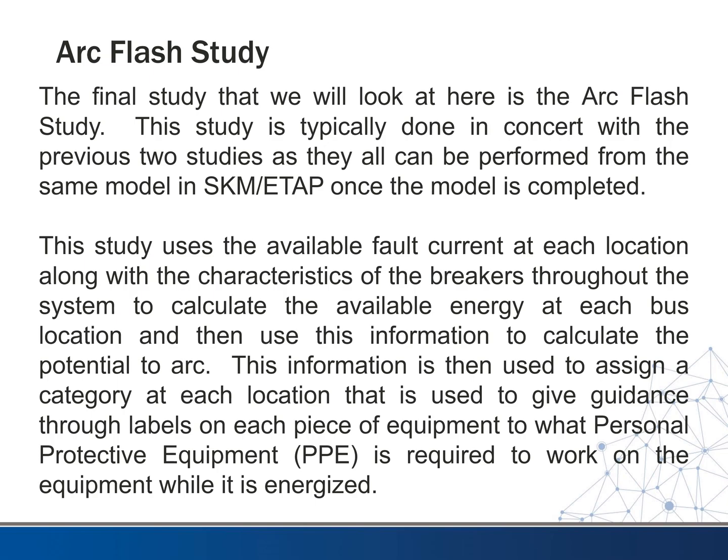This category gives guidance through labels placed on each piece of equipment as to what type of PPE — personal protective equipment — is required for an electrician to work on that equipment while it's energized and stay safe. It's a pretty important study. It is required by OSHA. If you have a facility and you notice there are no labels on the panels, you might mention that if OSHA shows up for a surprise visit and they don't see those labels, you will get a significant fine.